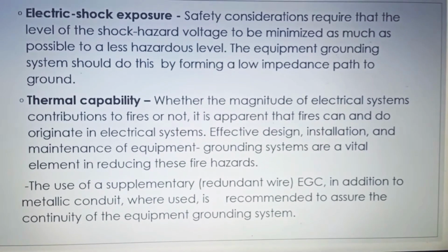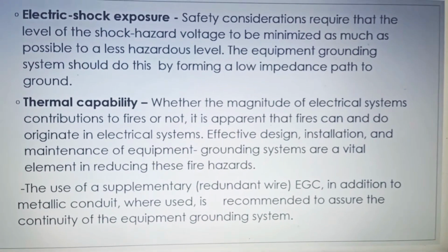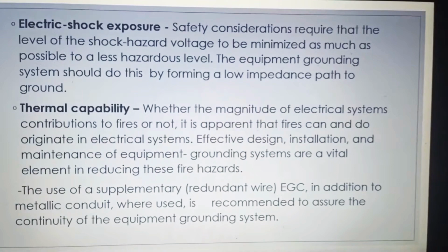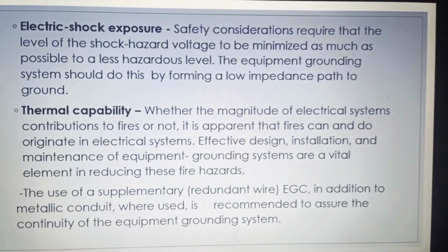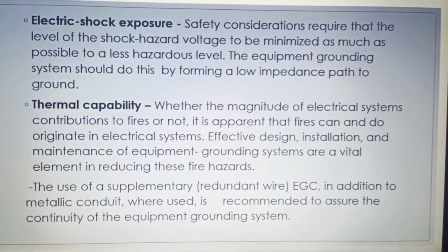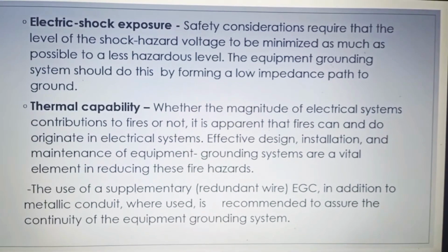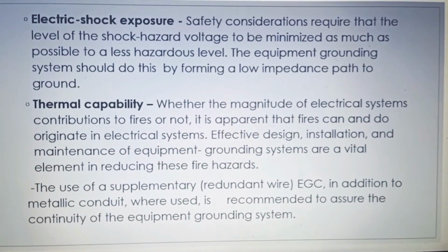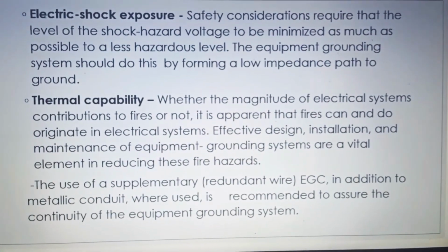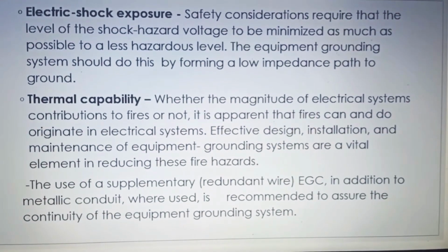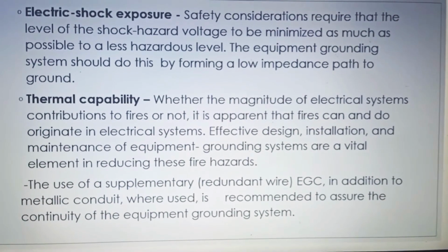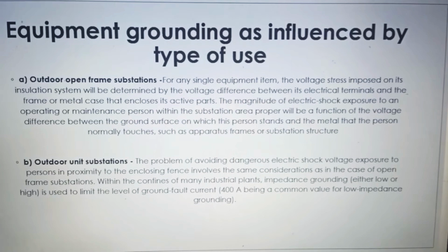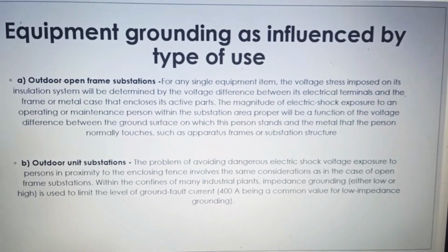Thermal capabilities. The grounding conductor must also function to conduct the available ground fault current without excessive temperature rise or arcing. The use of a large cross-section grounding conductor is not enough. All the parts of the fault circuit, including the terminations and other parts, should be capable of carrying the fault current without distress. Equipment grounding is influenced by the type of use.